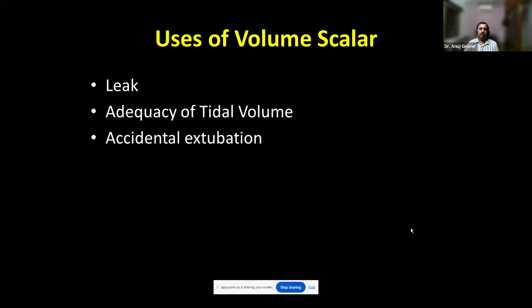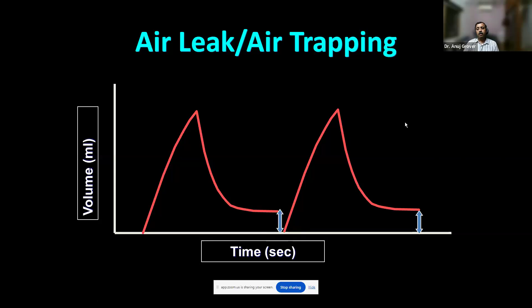How will the leak look like? So your inspiratory tidal volume goes up. At the end of expiration, the volume does not reach the baseline. So there is a leak of a few ml that you can judge from this. So where has that air gone? So either that air has leaked around the tube, or there is an air trapping, like say in a ball valve mechanism in a meconium baby. Okay, so whatever is the inspiratory volume, the expiratory volume is less than that. That's what the flow sensor is telling you. So that volume has gone somewhere. Most likely it is leak around the tube. So if the leak is very high, say more than 25-30%, then the volume targeting mode can be difficult to use. So then you might think about using a bigger size tube.